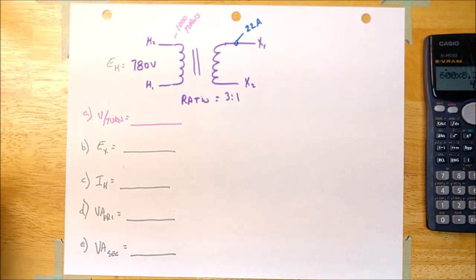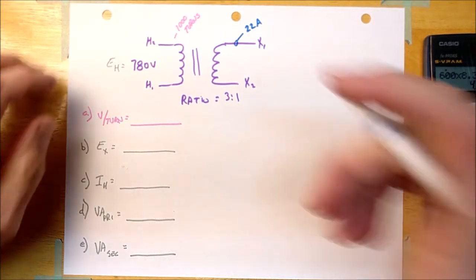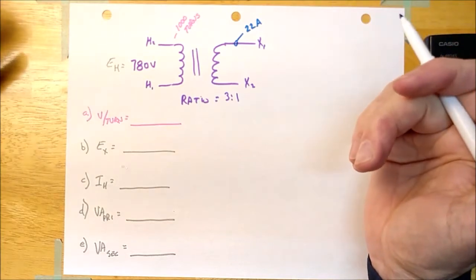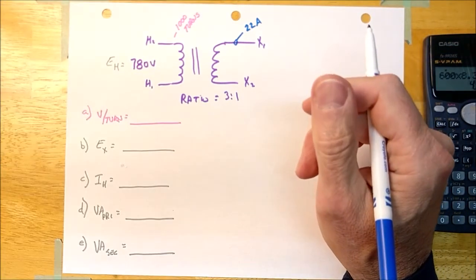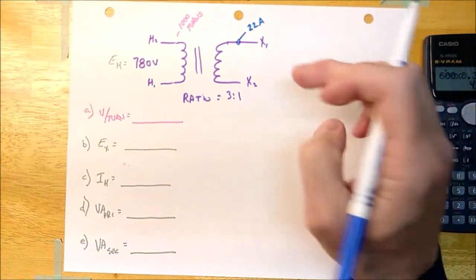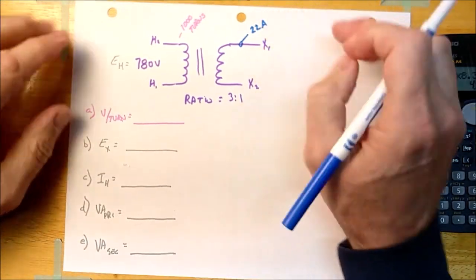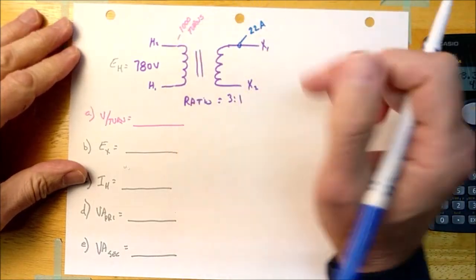All right guys, so here it is. It's a 3-to-1 ratio transformer. High voltage is 780 volts. The low voltage is I don't know what, but we do have a current on the low voltage side, it's 22 amps. Looks like the primary, or the high voltage side, has 1,000 turns.